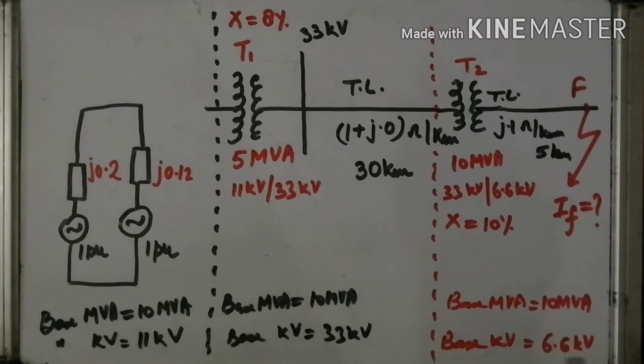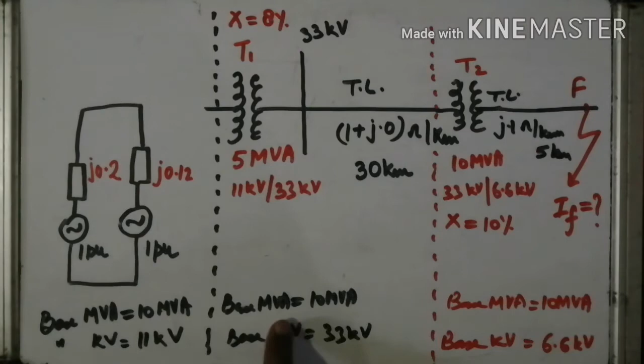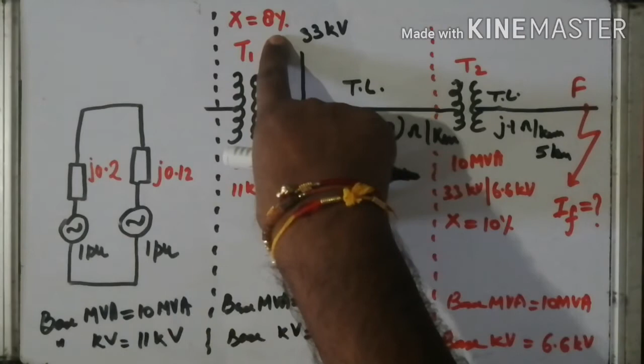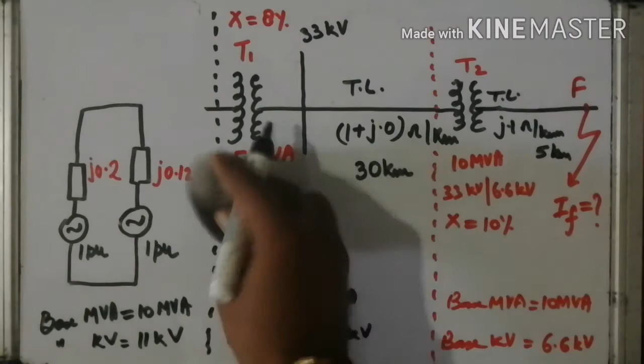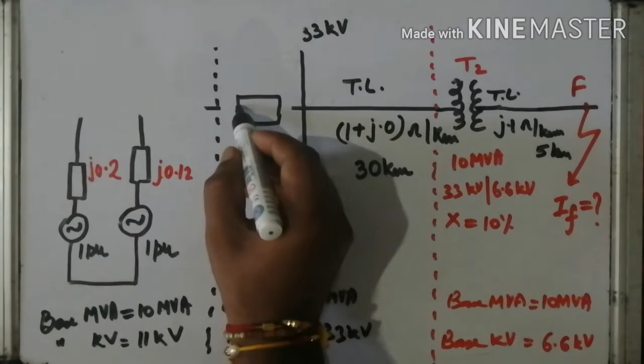After that, see this portion, transformer number 1. Transformer number 1 having the rating of 5 MVA, but here the base value is 10 MVA. That's why in the place of 8%, we are going to take 16%. Right? 16%. So for this portion, there is a reactance having the value of J 0.16. Is it okay? These two transformers are operating in parallel. This one for the transformer. Now for the TL.